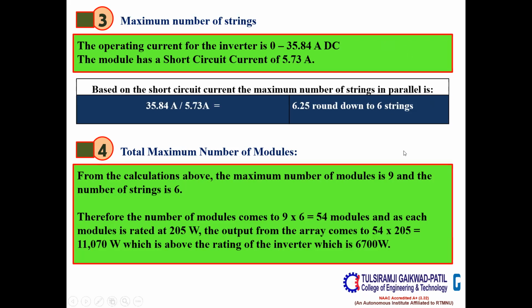At the same time, the rating of one single module which is given in this particular problem statement is 205 watt. So 9 multiplied by 6 would give you 54 modules. 54 modules multiplied by 205 would give you 11070 watt. But the inverter rating which is provided to us is 6700 watt. So this is the disconnect here. Step number 1, step number 2, step number 3 is fine, no issues.